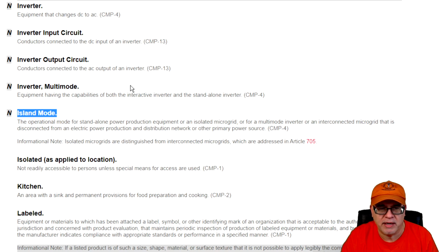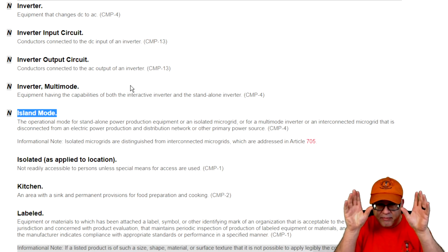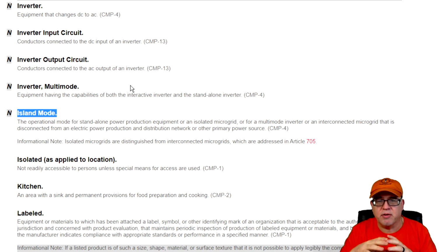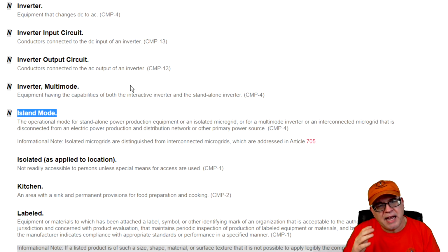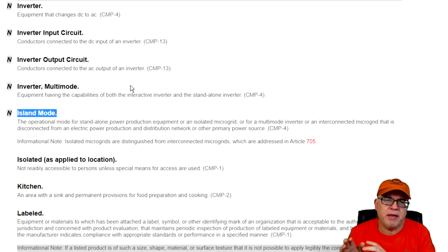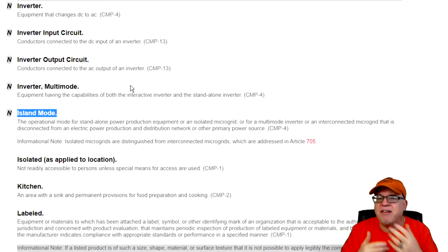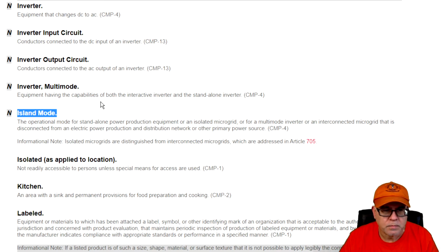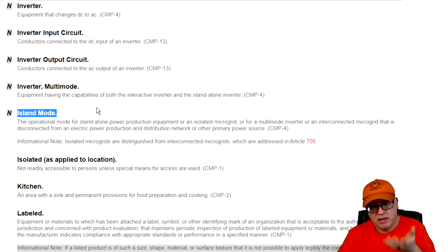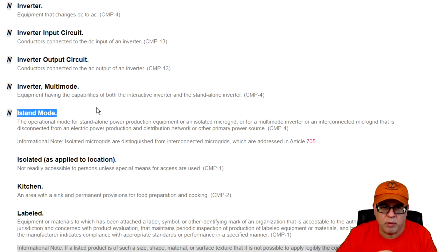Then you've got what's inverter output circuit. And again, that's conductors connecting to the AC output of the inverter. So I've got a photovoltaic system and the DC is coming from the strings and arrays coming down through a disconnect into the inverter. And that is going to be through the inverter input circuit. And then on the output circuit, it's converting it, if you will, or inverting it, I should say, over to AC, right? And then it's coming out. So that's the AC output. Important to understand these references because when you get up there, there's applications of percentages and things that have to be applied to some of these values, and you need to know what an inverter output circuit is. You need to know what an inverter input circuit is. So when we get up there into 690, these things, for example, will make more sense, okay? And it's obviously not just in 690 because it's in 100, so that means it has to be in more than one article. So there are other aspects where it will be.